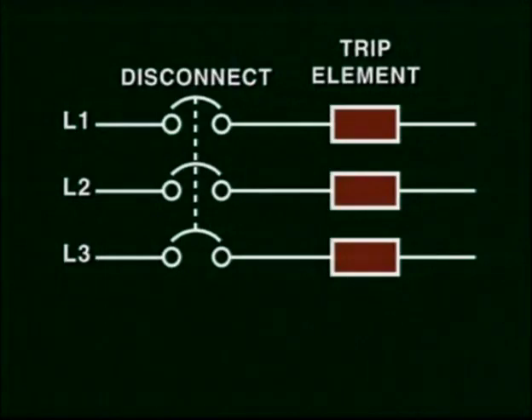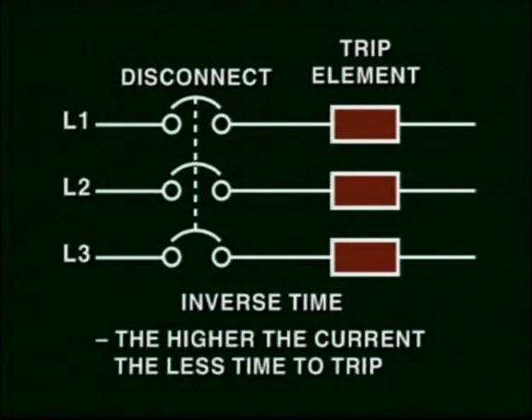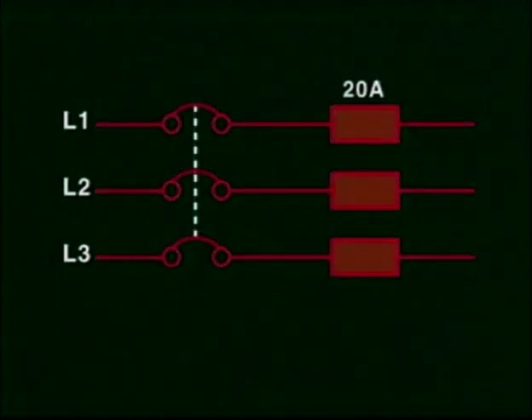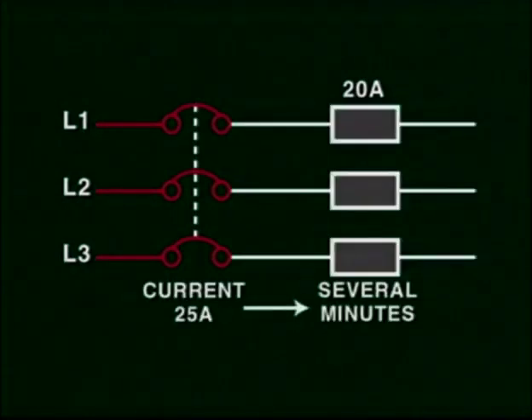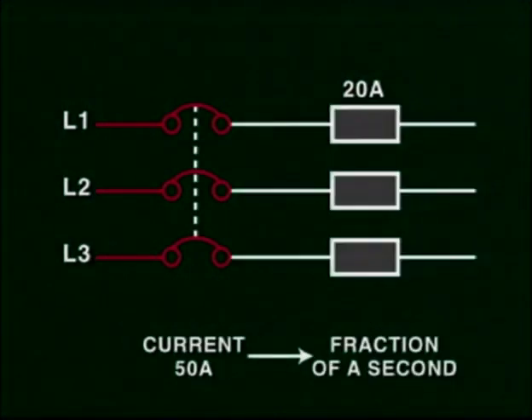Circuit breakers use two types of tripping elements, a bimetal or thermal and a magnetic, and in some cases both. These devices may trip in an instantaneous manner or in what's called inverse time fashion. The inverse time simply means that the time it takes the breaker to trip is inversely proportional to the amount of current. The higher the current, the less time it takes to trip. For instance, a 20-amp breaker may take several minutes to trip at a current of 25 amps, whereas if the same breaker is subject to a 50-amp current, it will trip in a fraction of a second.